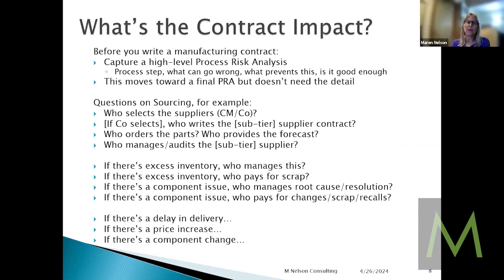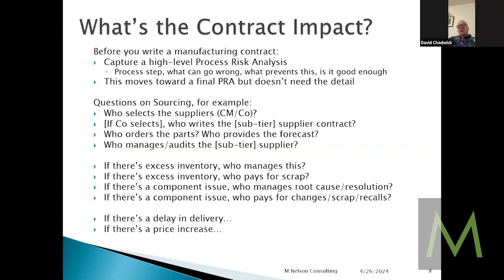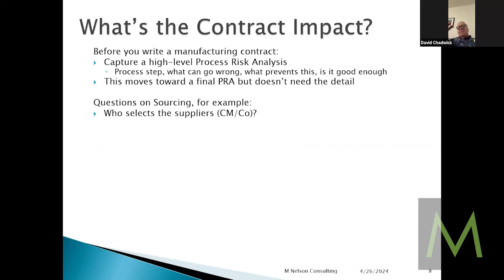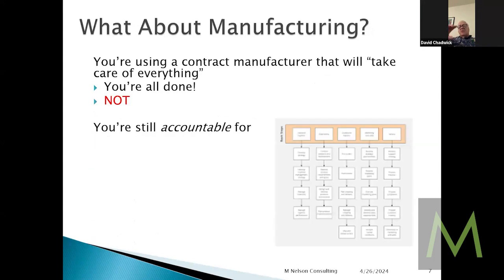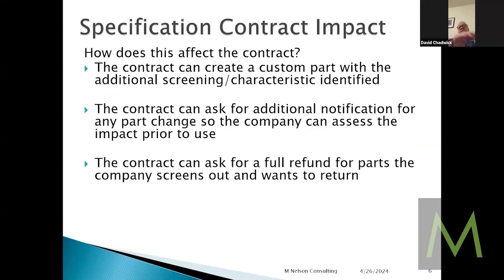I don't think that we are, but having made complex medical products like defibrillators, some of the products that we buy to put in a defibrillator are based on our assessment of the manufacturer's specification. And that's acceptable. Then in our purchasing agreement, we say we will accept product component X from you with these given specs that you created. And the next paragraph says, if you make changes to this spec, you must inform us.